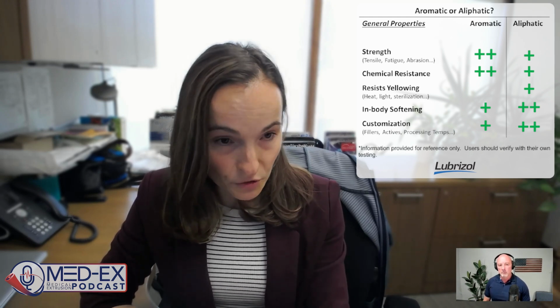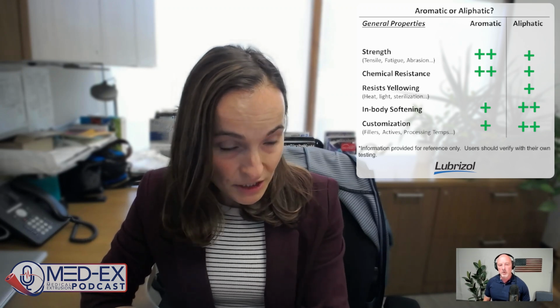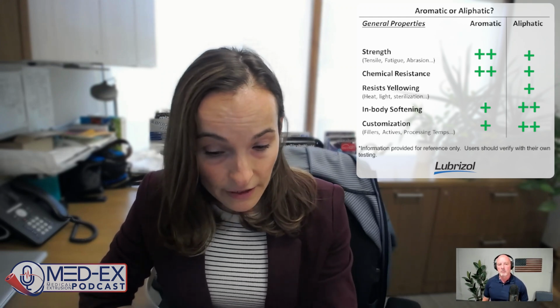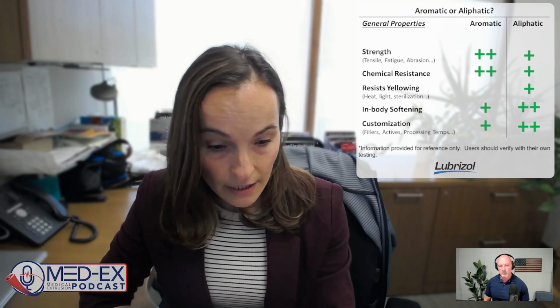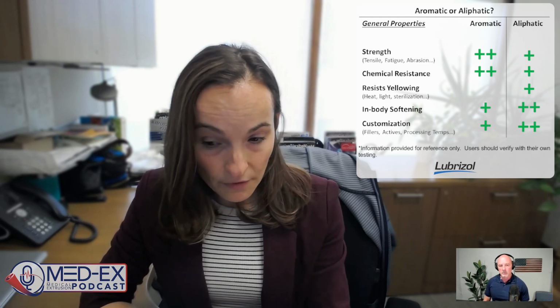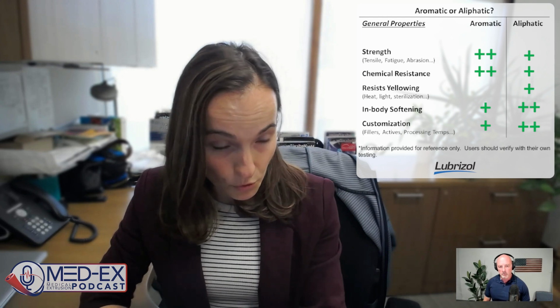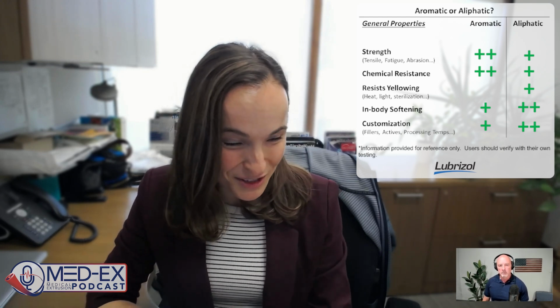With an aliphatic material, one of the main benefits is that it's a non-yellowing type of isocyanate. So you will maintain your clarity and your color much better, especially if you're planning on gamma sterilizing, for example, having exposure to radiation or UV light. The other thing to note about aliphatic is that it is a less tightly packed structure. So TPUs made of aliphatic isocyanate can actually soften more in the body, and you can see that as either a strength or a weakness, depending on the application. Okay. Interesting. So the aliphatic is less prone to the yellowing with UV light. Yes. And the sterilization, that's interesting as well.